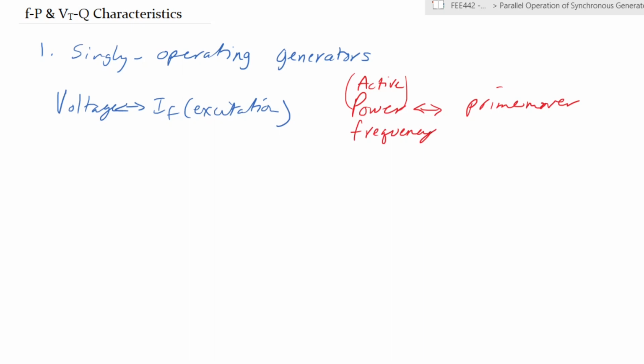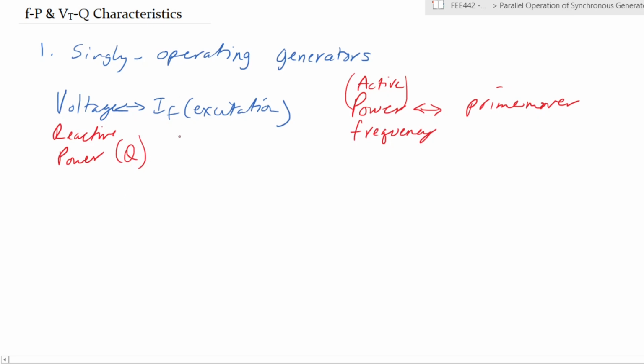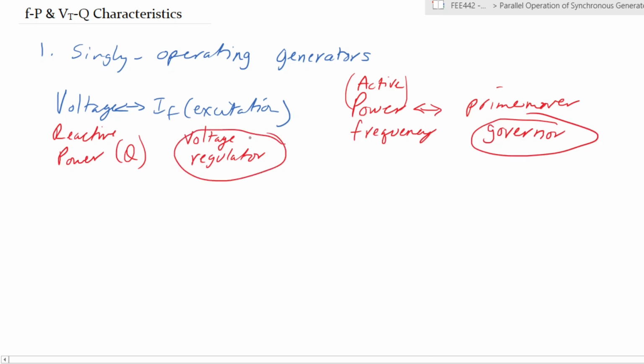So one additional thing that we would want to include here is that while the prime mover affects active power and frequency, the excitation of the generator affects the voltage as well as reactive power, or Q, right? And IF, or excitation, in practical generators is called the voltage regulator system. And on this side, active power, or the prime mover, is regulated by the governor. So these two are the main means by which we alter the operation of the generator in terms of the loads that we need to supply.